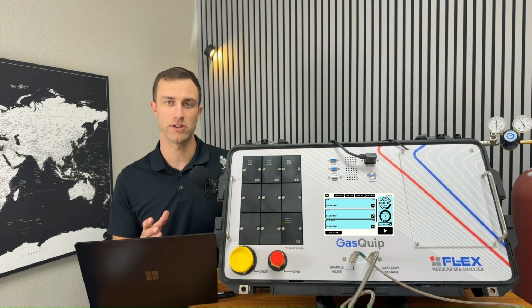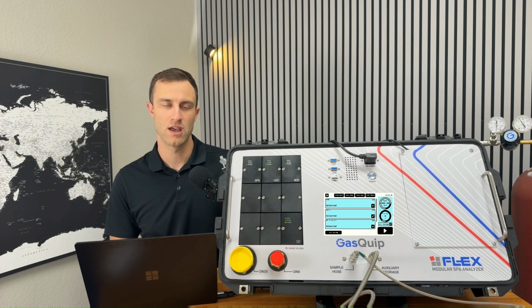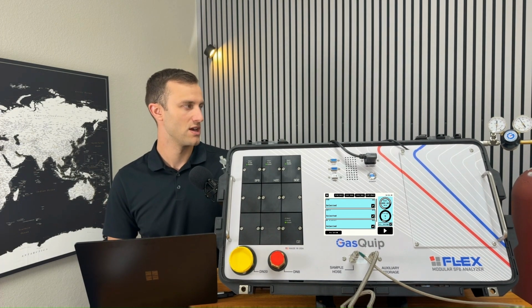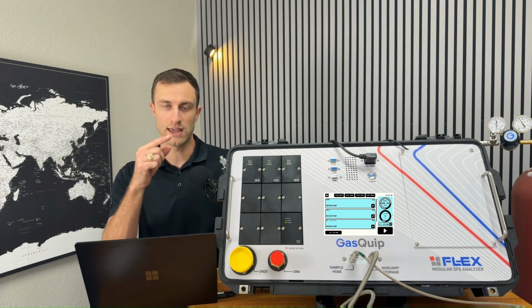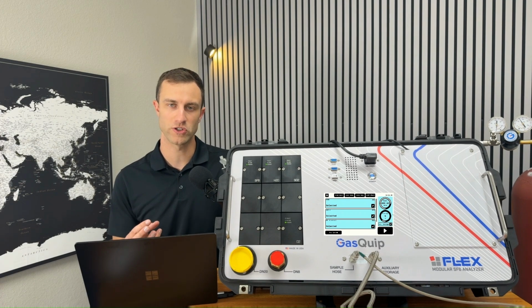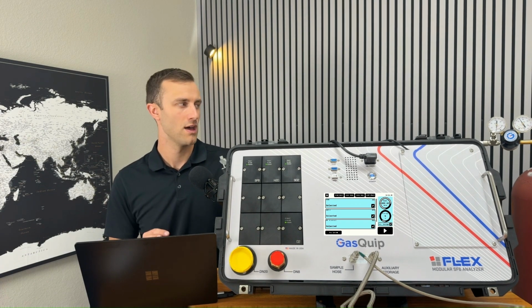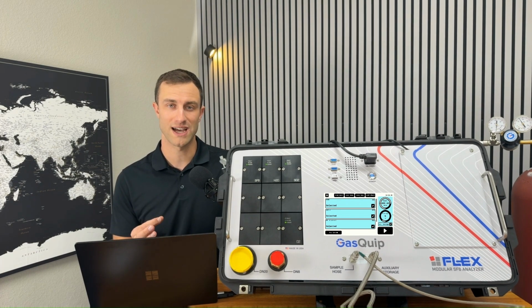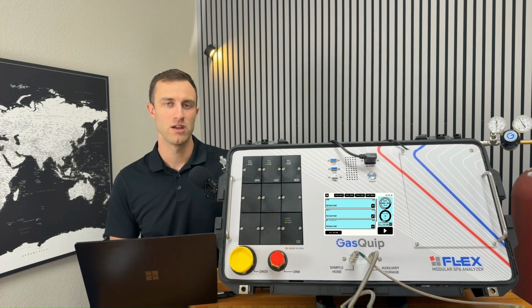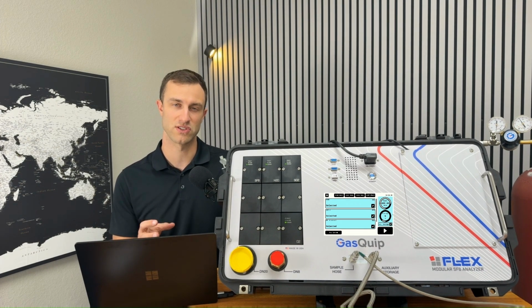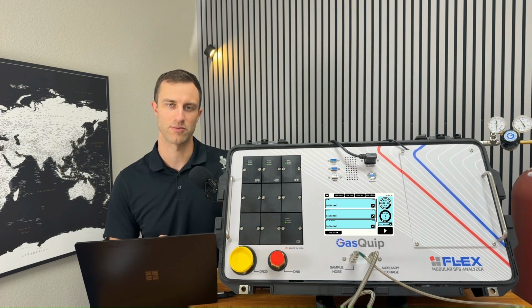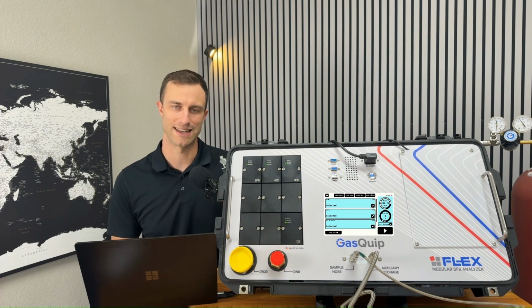As far as material compatibility goes, always use a PTFE or Teflon style lined hose like the one that we provide, the stainless steel braided hose, and stainless steel or brass fittings, and avoid using rubber anywhere in the gas path for the sample, because rubber tends to hold on to moisture. It absorbs and adsorbs moisture into the sample. Also avoid using any PTFE sealant, the goop or Loctite type sealant. Always use PTFE tape. The reason is that the PTFE sealant can gunk up the sensors and off gas into the sensors in the system over time. So try to avoid anything that can off gas any type of VOCs or any type of materials into the system, to keep everything clean and nice and fresh.